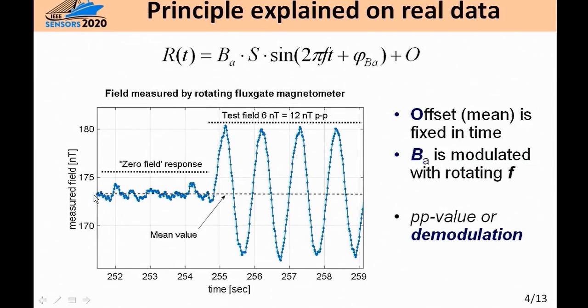Even in the graph we see that the average value is the sensor offset - we do not have to regard it. Our test field, in this case 6 nanotesla, results in a 12 nanotesla peak-to-peak modulated signal. So the only thing we need to do is either establish the peak value or demodulate with the help of the reference marks.